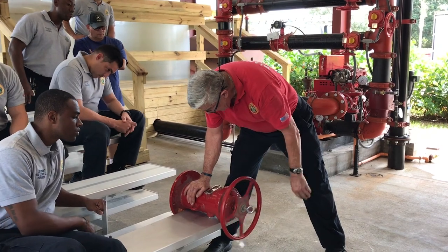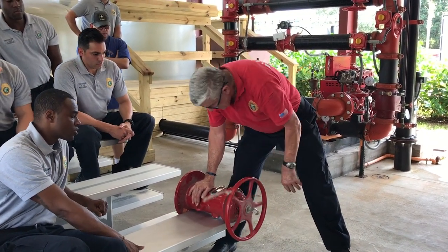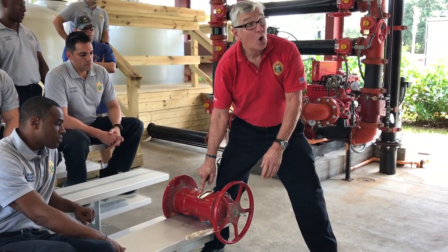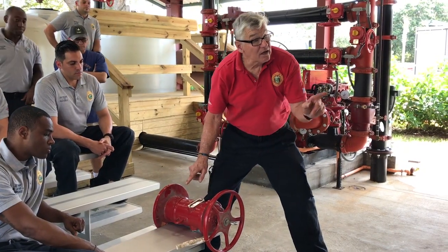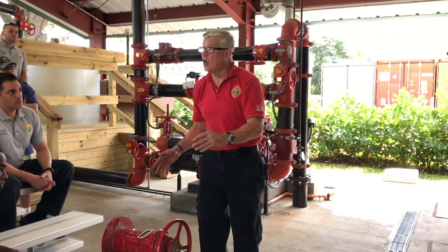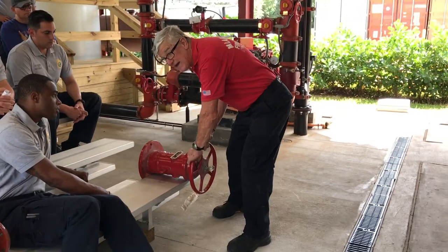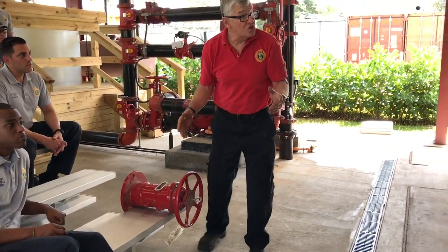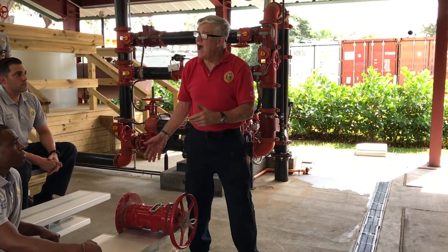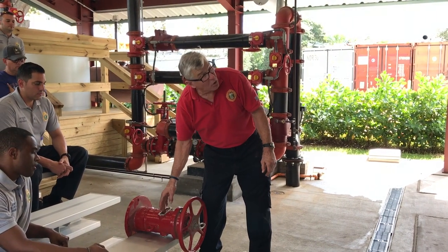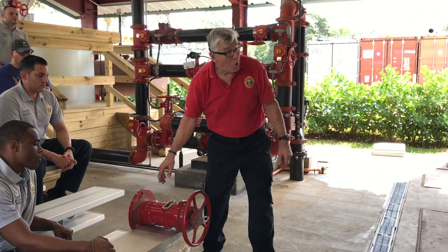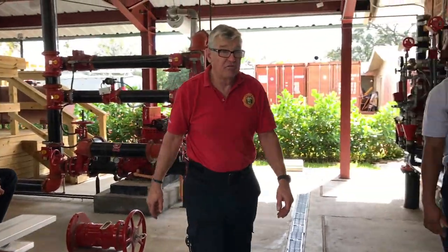If you will see a sign, for the sake of time, I'm not going to do it, that will say open or close. In a fire, even if it says open, give it a shot. It could be stuck. Make sure the valve is fully open, even though it says open here. Open or close. Wall post indicator valve.